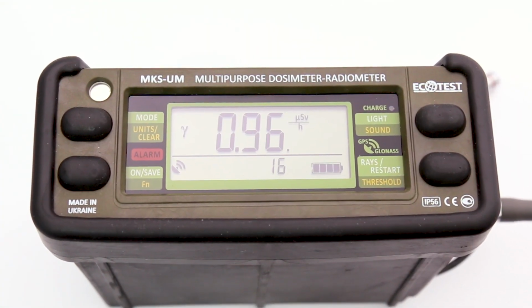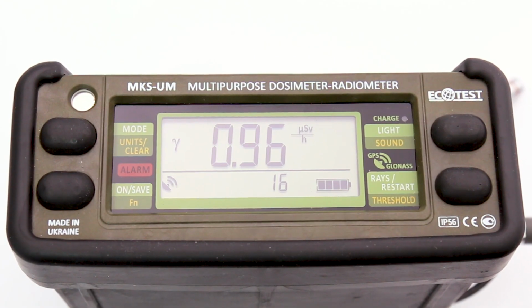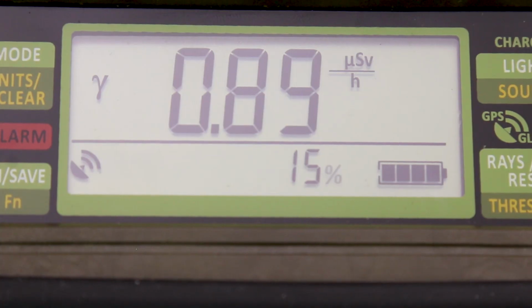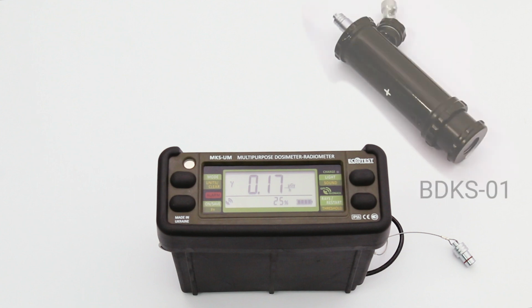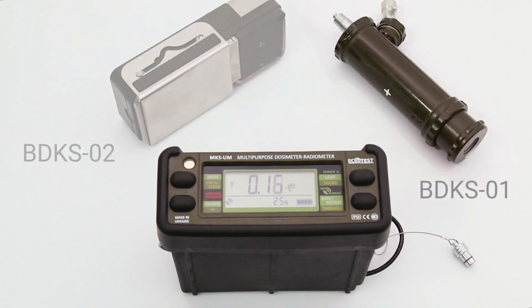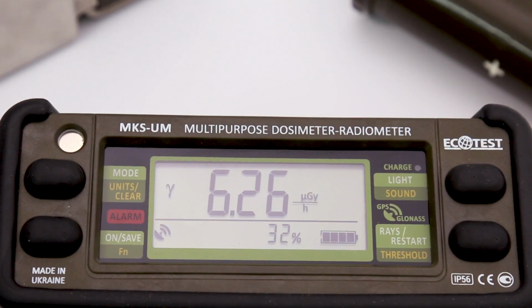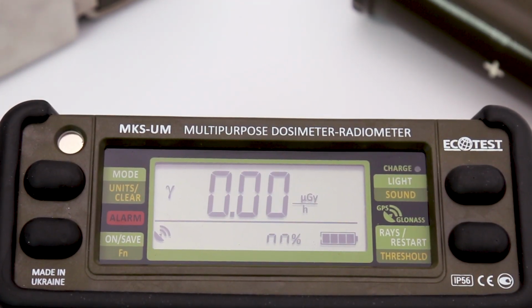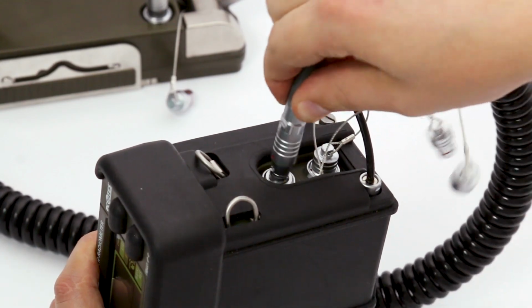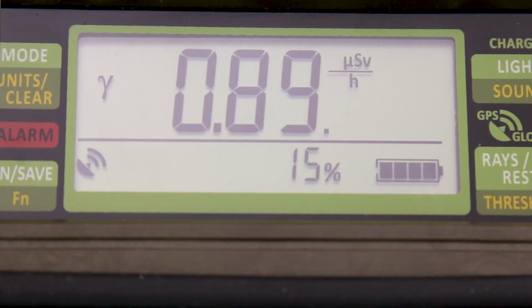The dose rate of the photon ionizing radiation can be measured by the detector, integrated into a dosimeter control panel, or by the BDKS-01 and BDKS-02 detecting probes. If none of the detecting probes is connected to the device, the dose rate is measured by the control panel. If one of the probes, however, is connected, it measures the dose rate, and the control panel displays the measurement results only.